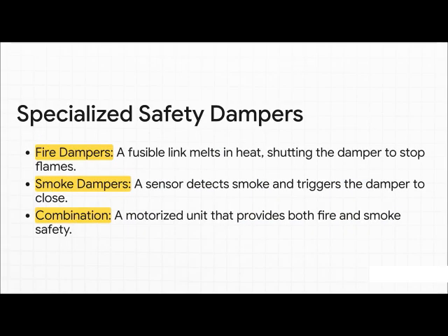Finally, we have to talk about some really important dampers that are all about safety. Fire dampers have a little link inside that's designed to melt if it gets too hot. When it melts, bam, the damper slams shut and stops fire from spreading through the ducts. Smoke dampers work the same way, but they're triggered by a smoke detector. These things are absolutely critical lifesavers because they stop a fire from spreading through the building's own lungs.